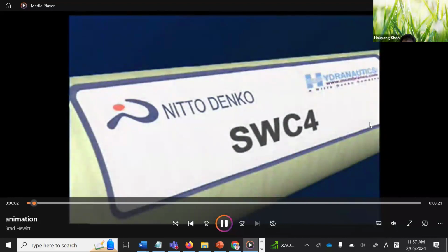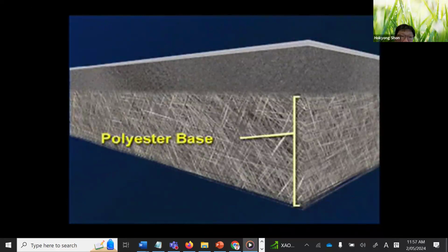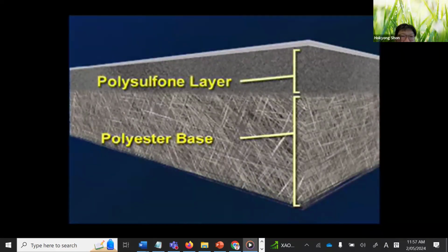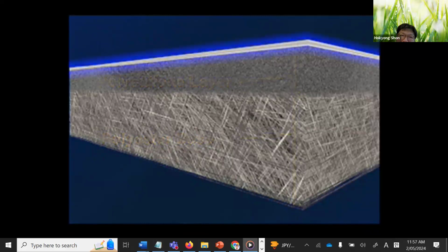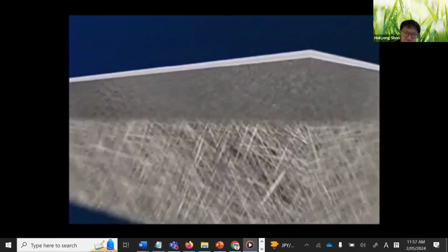To create our standard spiral wound membranes, we construct the flat sheet membrane using Hydranautics automated casting equipment. We begin the process with a fabric support base and then coat it with a microporous polysulfone layer. This provides additional support for the top 0.2 micron thick membrane barrier layer. This top barrier layer makes the actual separation to purify the water. The semi-permeable polyamide layer consists of a thin film of polymeric material, a few thousand angstroms thick, formed on a porous supporting material.